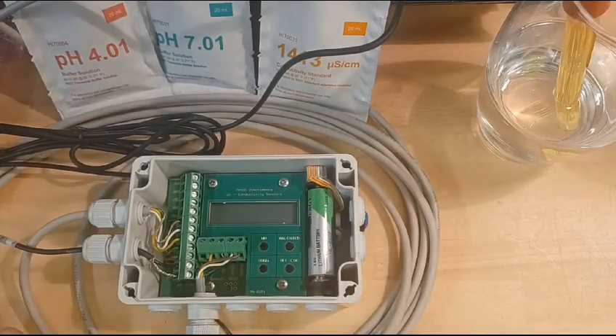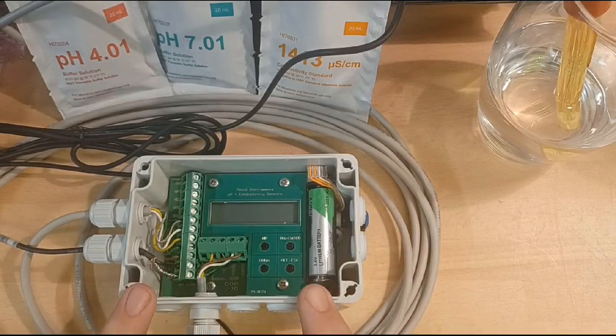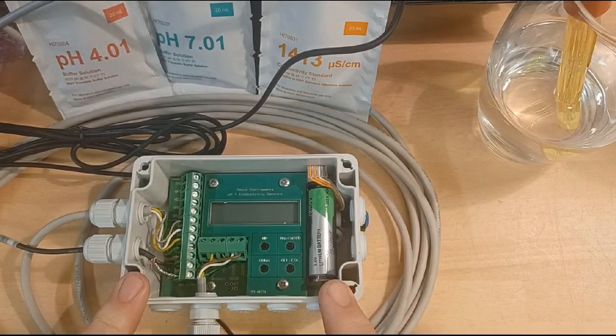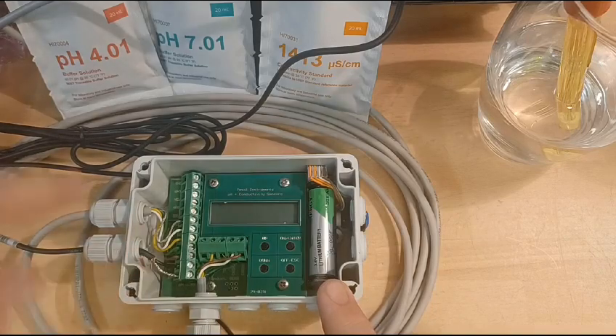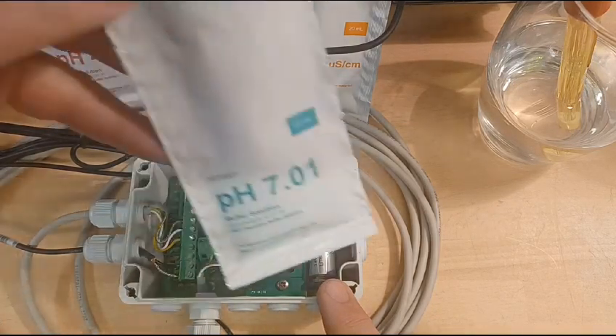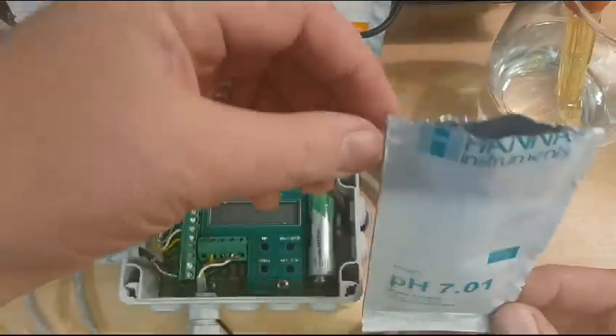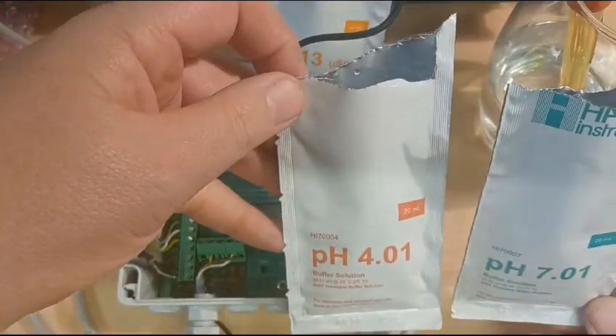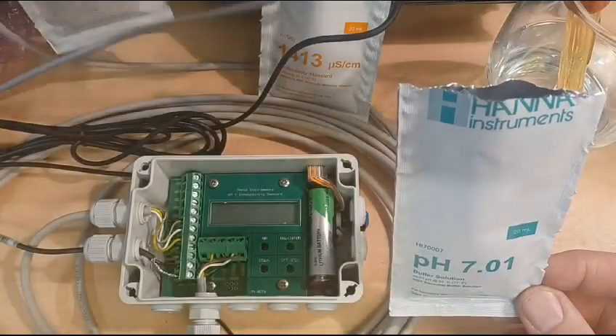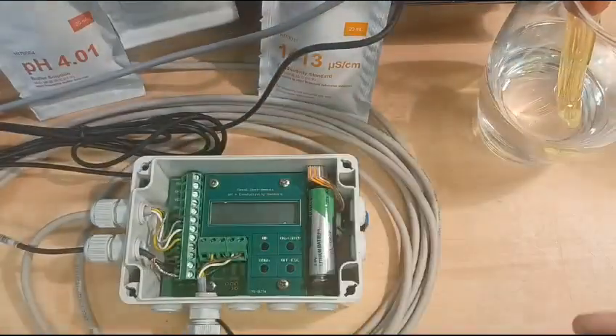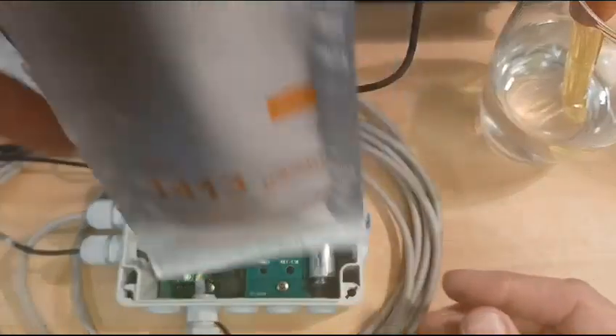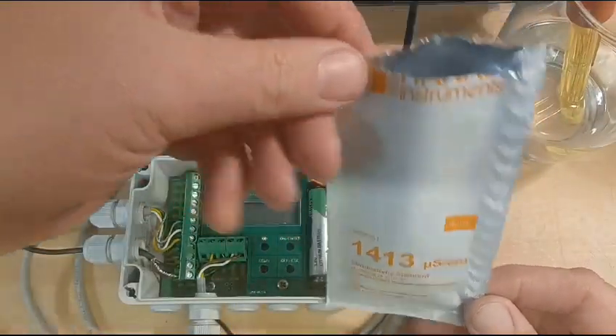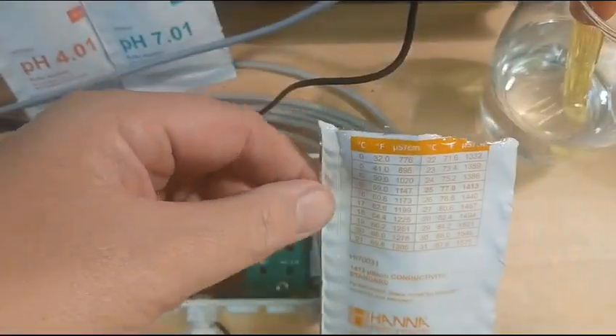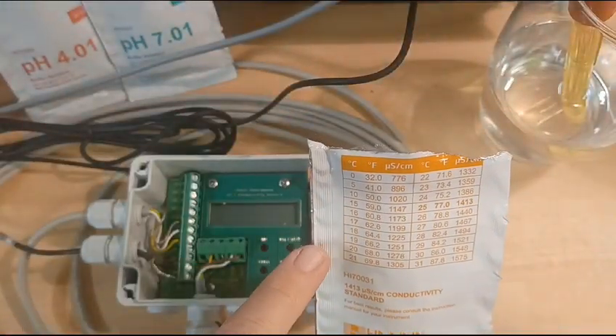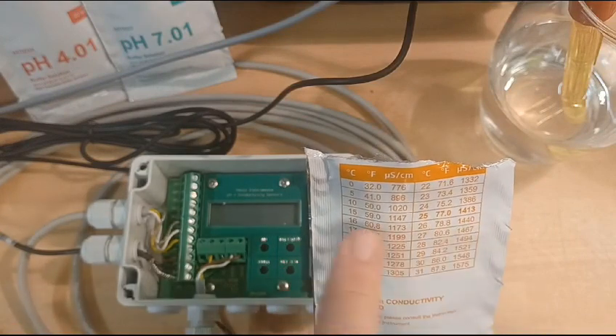Once the EC and pH sensor are installed into the interface box, you then need to calibrate the two sensors. With the pH, obviously we have a pH solution 7 and a pH solution 4, so we get in between the two. And then for the conductivity on the EC, we have the 1413, which according to the manufacturer is pretty much middle sort of standard range.